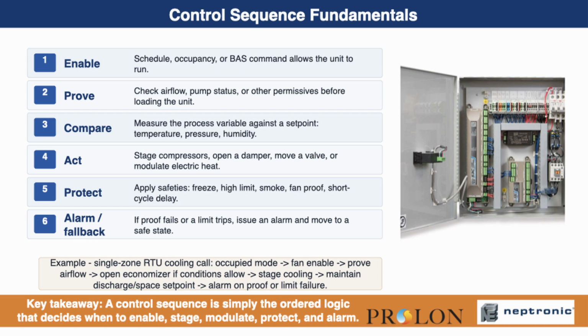5. Protect. The controller checks safeties such as fan-proof, freeze-a-stat if applicable, high-pressure or low-pressure trips from the unit, and short-cycle protection timers. 6. Alarm or fallback. If airflow proof is lost or a safety opens, the controller shuts down cooling as required, may keep or stop the fan depending on the sequence, and generates an alarm or fault condition. That is why sequence understanding makes troubleshooting more logical. It lets us ask where in the order the unit stopped behaving correctly.